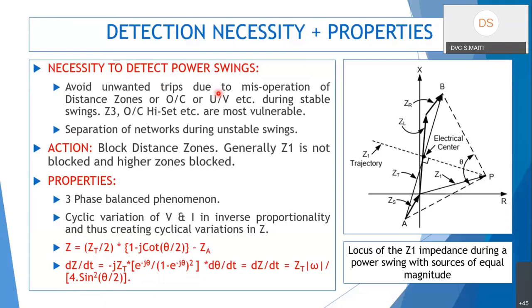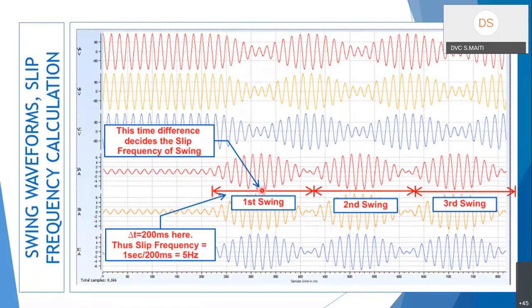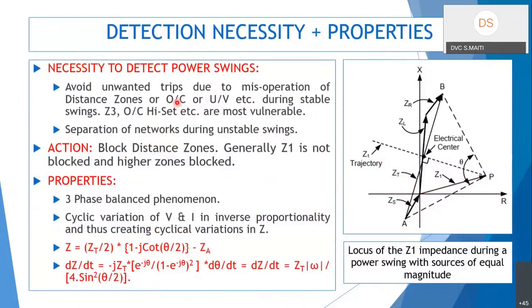We block our distance protection relay during swings. Misoperation can occur in distance zones, but also in overcurrent — as the current increases very high during a swing, instantaneous overcurrent protection might trip. Undervoltage protection may also get activated during a power swing. Zone 3, overcurrent high-set, etc., are the most vulnerable protections that might trip due to a power swing, which we don't want.